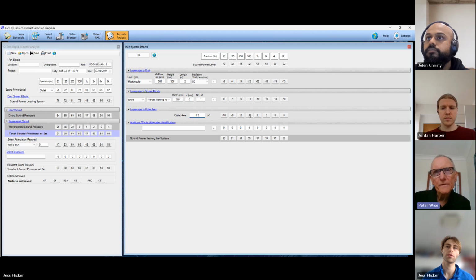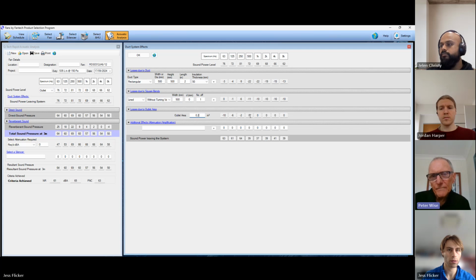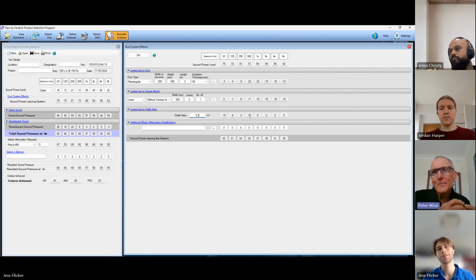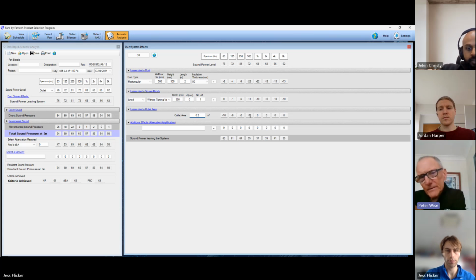Because it's related to end reflection. I'll try and explain this in basic terms. When the air is passing down the duct and it comes to an outlet where it's going to leave the duct, there's actually a resistance of the air to leave the duct - that's end reflection. So the smaller that is, the more resistance there is for the noise to come out. It's hard to explain, but imagine a sound wave passing down a duct - it comes to the end and it's got to find its way out. Some of the noise will come out and some will be reflected back, even though it's an open end. So it's just called end reflection, and it's a fact.